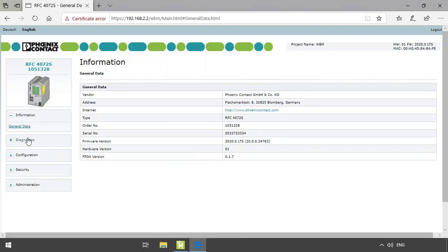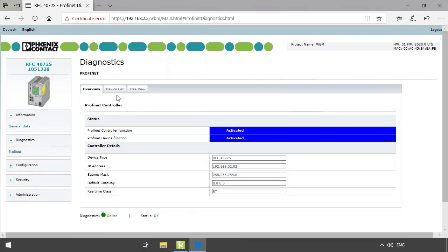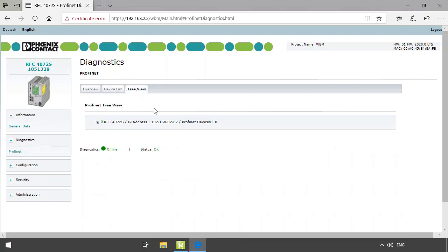In the diagnostics area we can get information regarding PROFINET. Here we have three different tabs: overview, device list, and tree view. In the overview tab we can get information about the functional status of the controller and the IP settings. In the device list and the tree view we can get details and status information of the connected PROFINET devices.